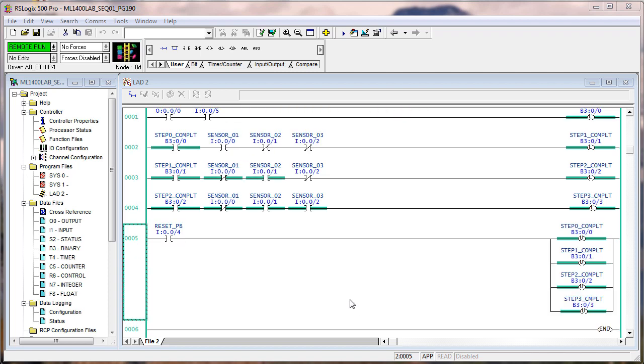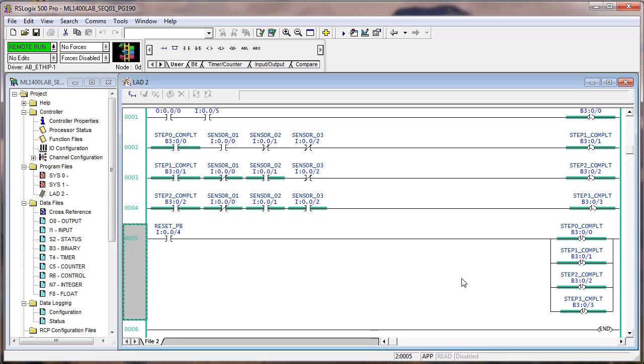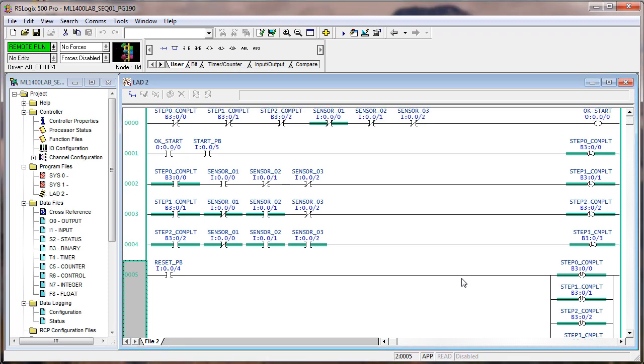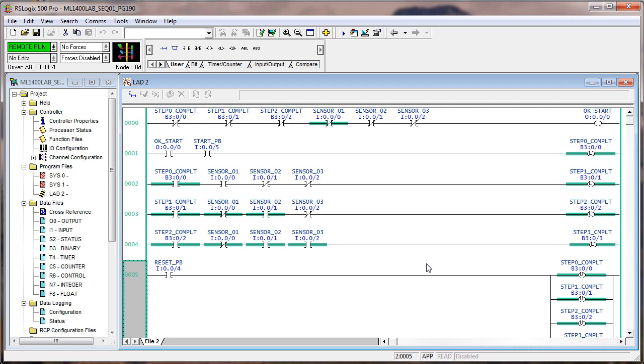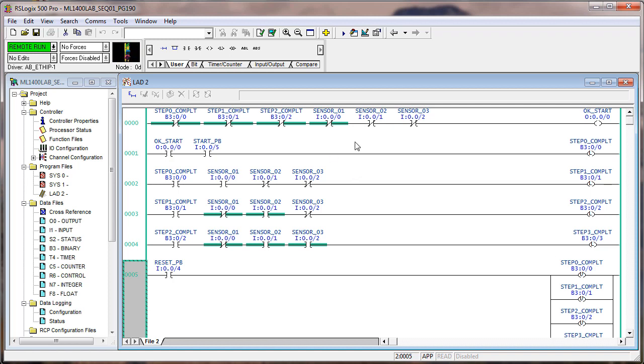So we added another rung that uses input four to unlatch these four bits. So now let's observe here. Notice that the state of these sensors is in the last step, step three. So when step three is complete, the machine stops. If we hit the reset button, that clears all these step complete bits, but we're not ready to start again until sensor two and three change states. Now it's okay to start again.